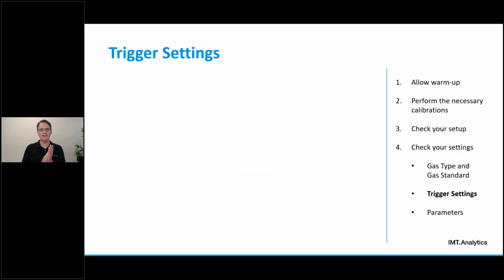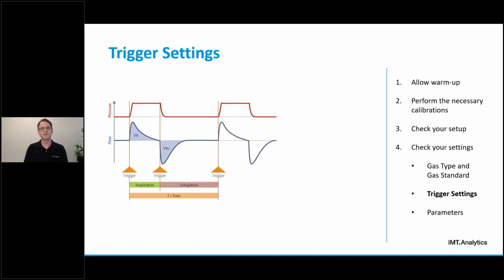Okay, next up, let's talk about trigger settings. That's another critical setting on your gas flow analyzers. Trigger settings are used by gas flow analyzers to identify the breath phases, inspiration and exhalation, of an ongoing ventilation. In most analyzers, you will see the terms start and stop, also called end trigger. This relates to the inspiratory phase. The start trigger is used to determine the start of an inspiration phase, while the stop or end trigger is used to detect the end of an inspiration phase, which also indicates the transition from inspiration to exhalation. And with the next start trigger, the next breathing cycle starts.